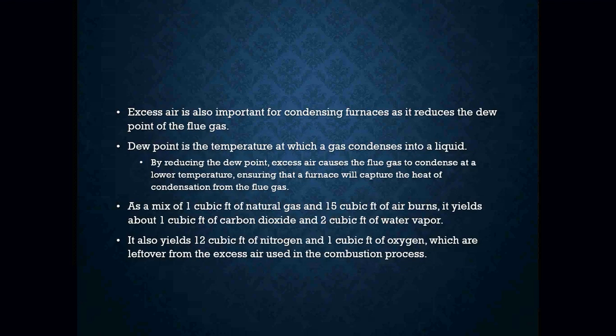Excess air is important for condensing furnaces as it reduces the dew point of your flue gases. Dew point is the temperature at which a gas condenses into a liquid. By reducing the dew point, excess air causes the flue gases to condense at a lower temperature, ensuring that the furnace will capture the heat of condensation from those flue gases.